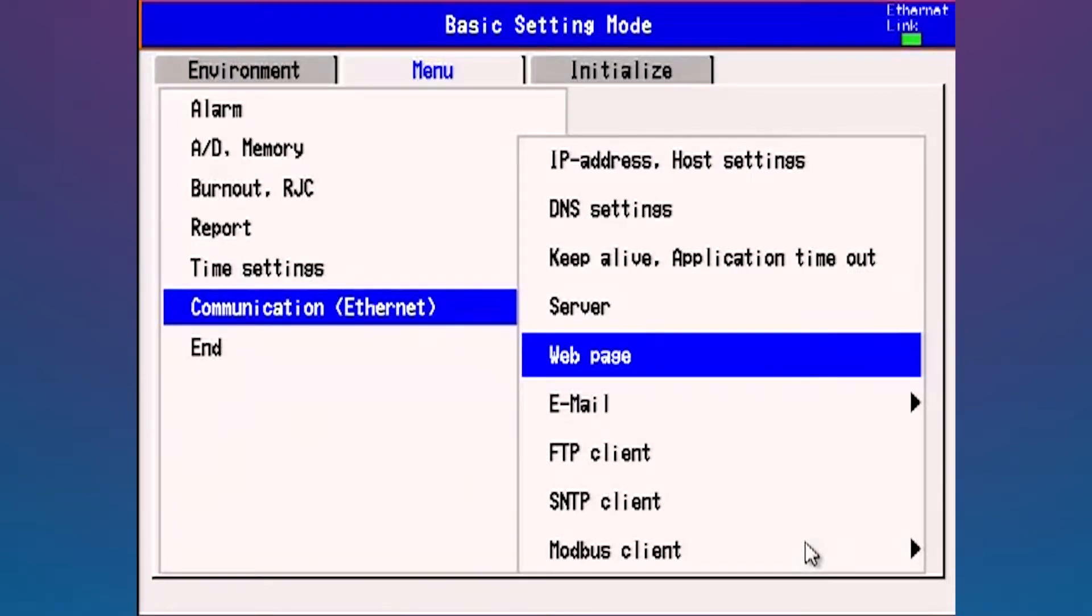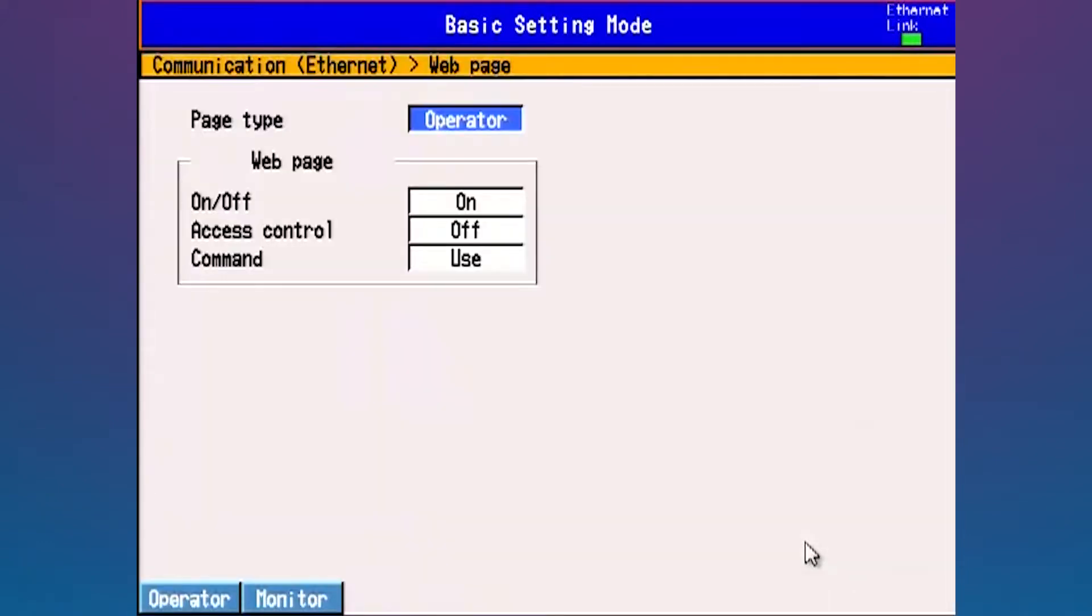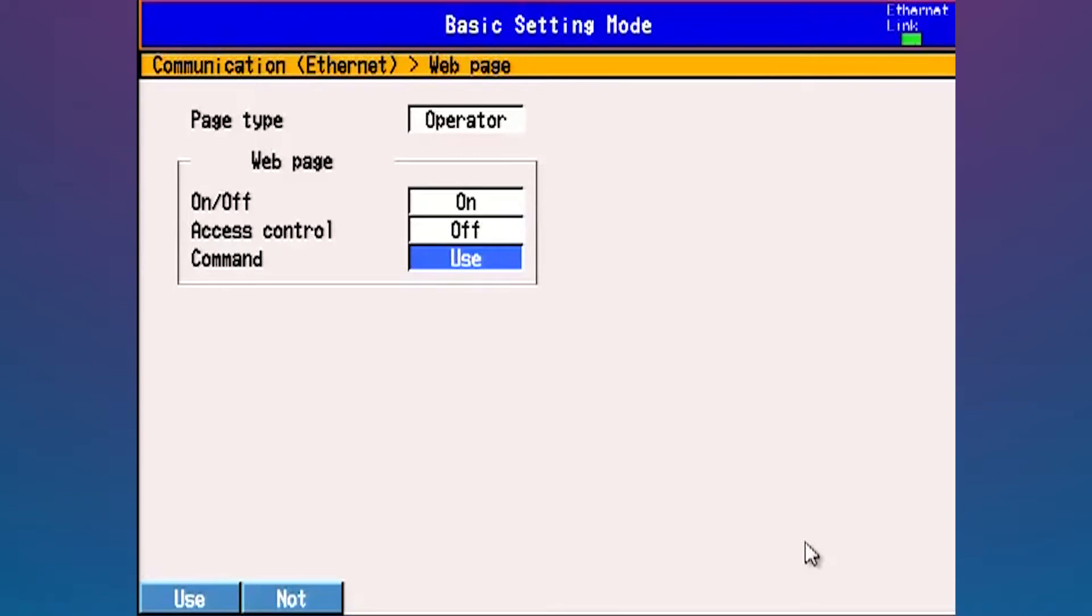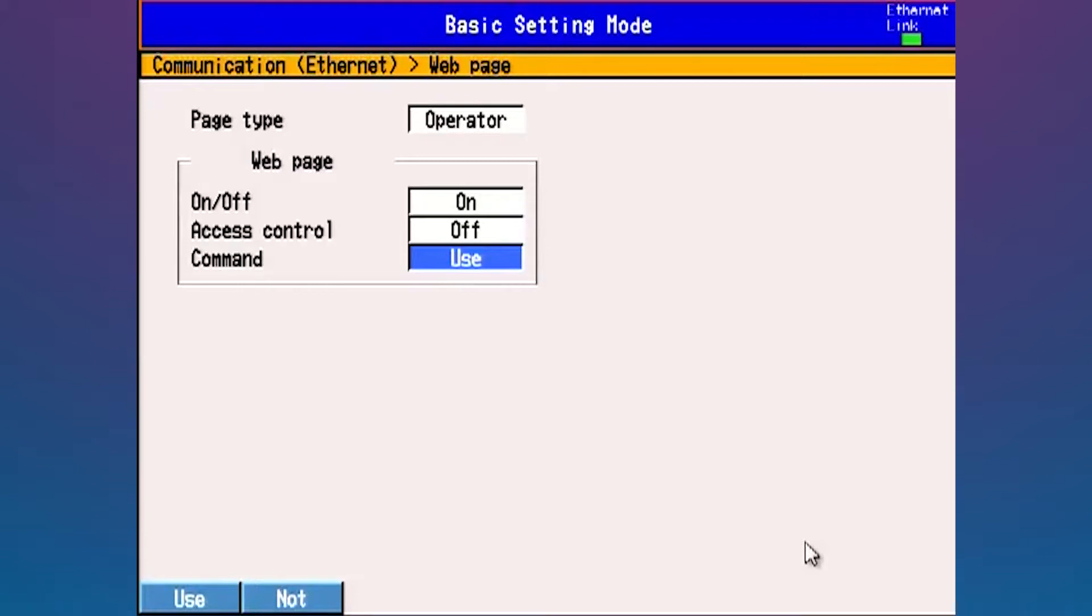One other thing that you may want while you're in here is to go to web page and set your settings to operator on and use. This will allow you to browse to the MV across your network by going to your internet explorer or whatever you use for a web browser and typing in the IP address of the unit: 192.168.1.204. If you want the full access to the display wheel for navigating, you can type in the IP address and then a forward slash operator.htm. That'll bring up the operator screen so you can navigate around the unit.